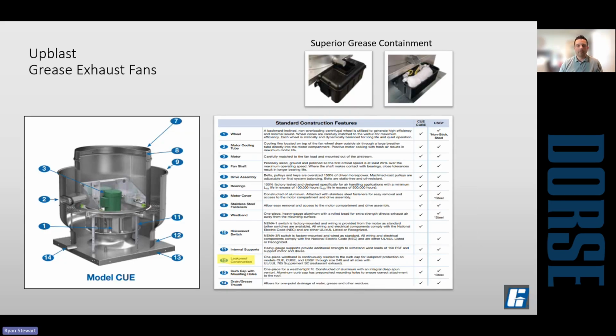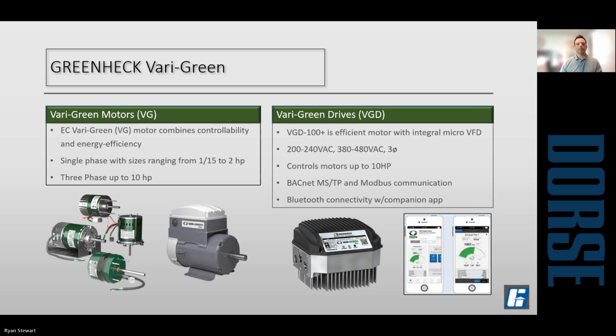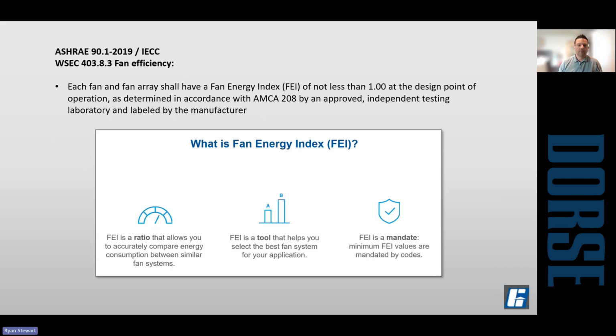This is the most common. A couple of the nice design benefits with the Greenheck is this outer band here. It is all one piece, stamped construction, and then the base of it is robotically welded down here, so you get a good leak-proof construction. And then they have a nice grease containment system to go along with it. As far as motors, if you're familiar with Greenheck's products, they do the Vari-Green EC motors. They have single phase up to 2 horsepower and 3-phase up to 10 horsepower. And they also integrate Vari-Green drives that go along with those on some of the larger ones.